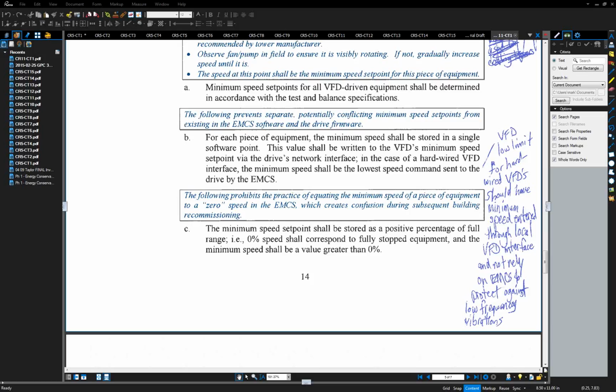Yeah, actually, I was rereading this comment, and what it was about was that we shouldn't rely on the BAS system to provide a safety. If the intent was to have a safety for the lowest speed, that should be done at the drive itself. And of course, for hardwired VFD, it says it's the lowest speed command sent to the drive by the EMCS. So it made it kind of sound like we would have a lowest speed stored in the building automation system rather than at the variable speed drive, and it would routinely refresh back down there. You can do it one way or the other.